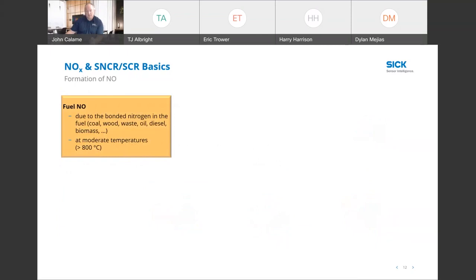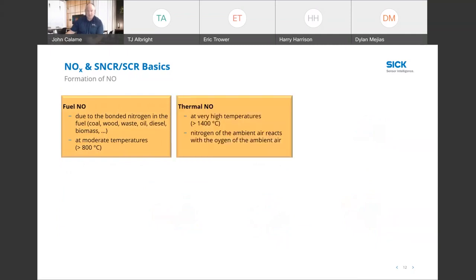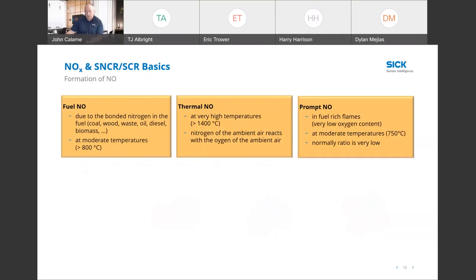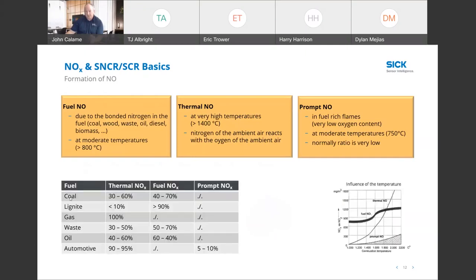So the formation of NO, nitrogen oxide: there's fuel NO, which is bonded in the actual fuels themselves. Whether it be coal, wood, waste, oil, diesel, whatever the fuel type is, it has a resident NO component within it. And then also thermal NO. At high temperatures, NO can be created. And then there's prompt NO that can come about when you have incomplete combustion or fuel-rich combustion. And then this lists out the different contents of the thermal, fuel, and prompt NOx for the different fuels.